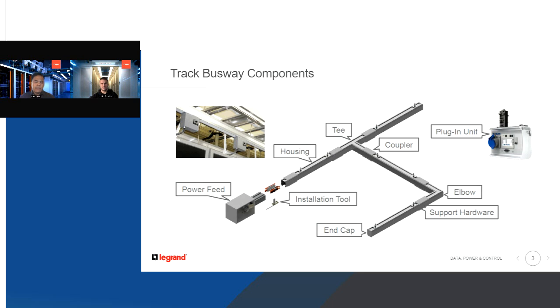Just to give you a picture of how the Busway components are comprised, this slide shows the different parts and pieces of a Busway. You start off with the in-feed down on the bottom left, where you bring in your power conductors to power the Busway system. That in-feed has a 1-foot Busway section attached directly to it, which attaches through a splice kit to the rest of the busway system.